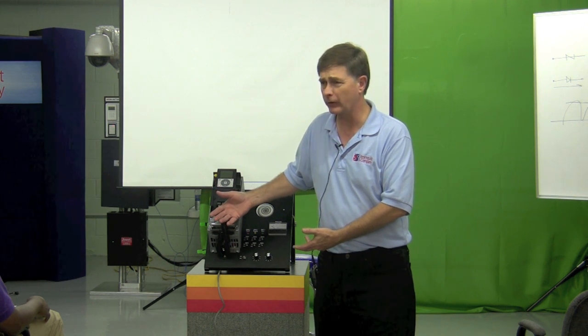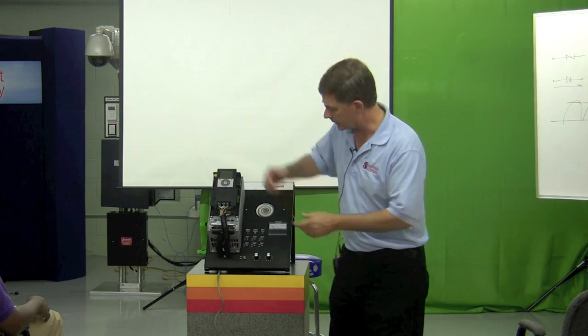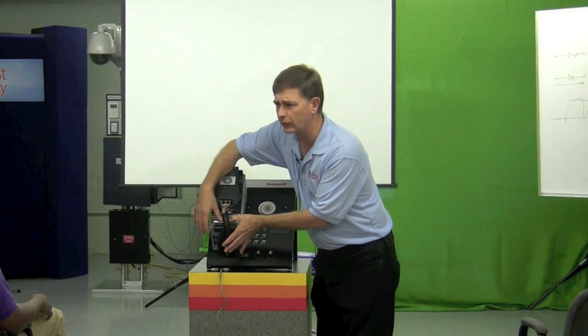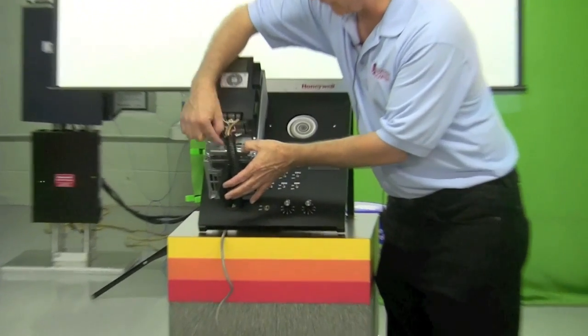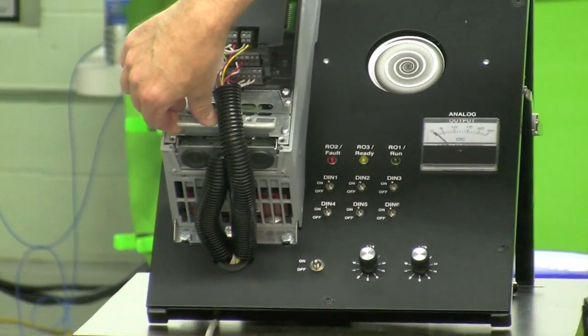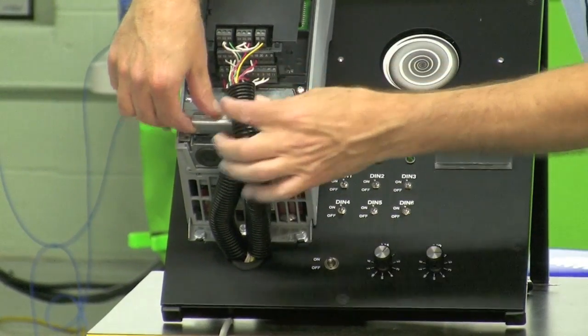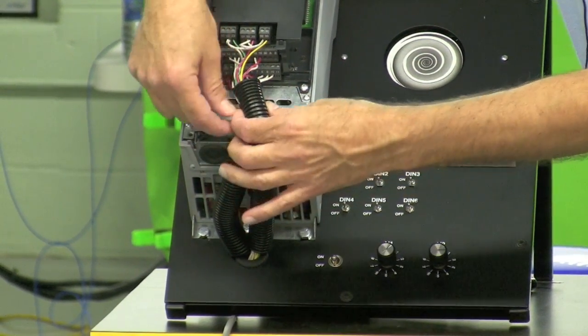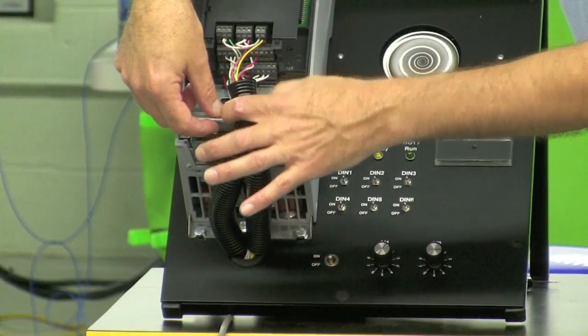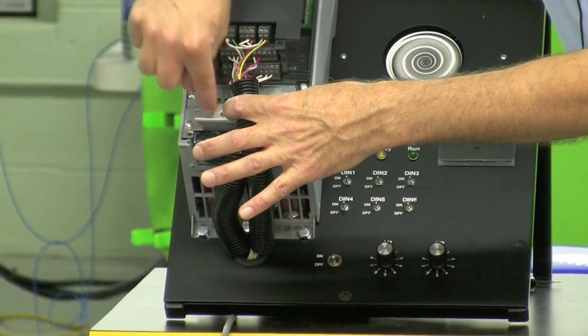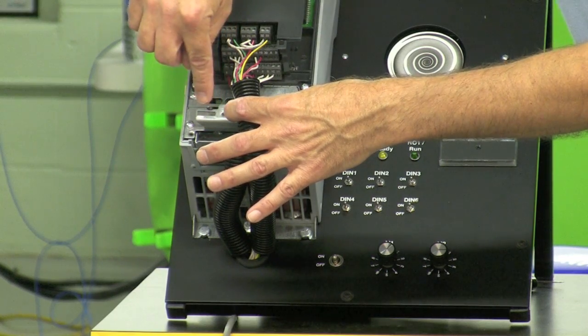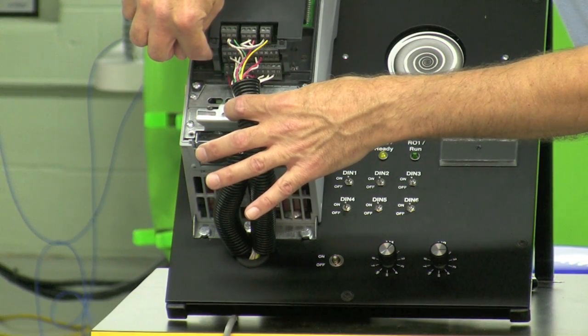Wiring-wise there's no mystery — it's pretty straightforward. The only thing to note is when you bring your signal cable and control cables in, you want to use shielded cable. When you run that shielded cable across the bridge strap, expose the shield and strap it down so you ground the signal to the chassis. A good ground is good, so if you have a good signal coming in it's pretty easy to do.